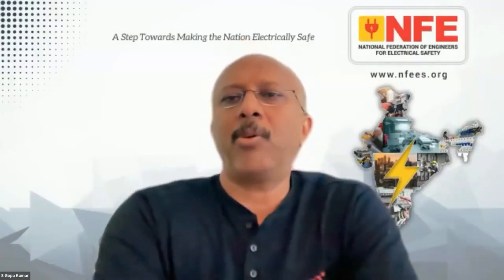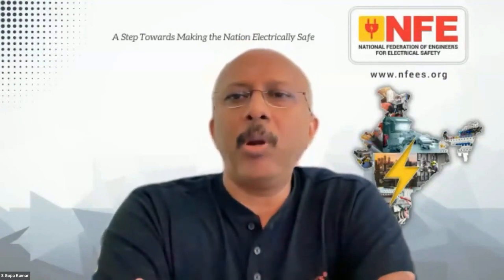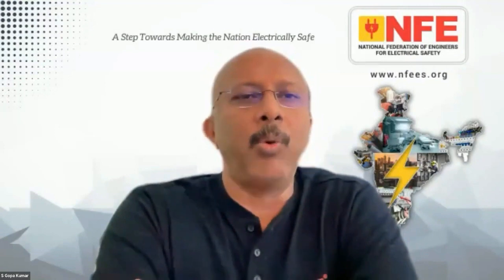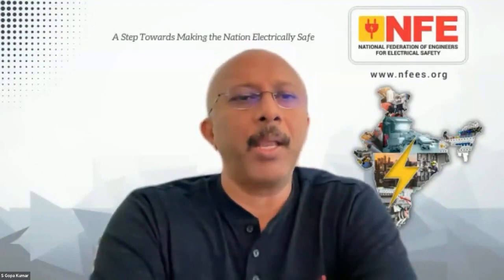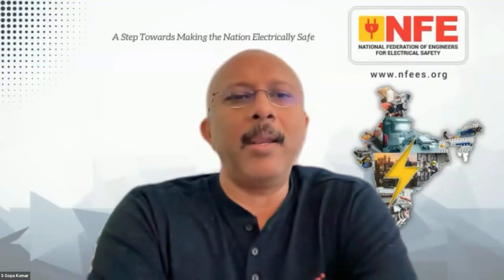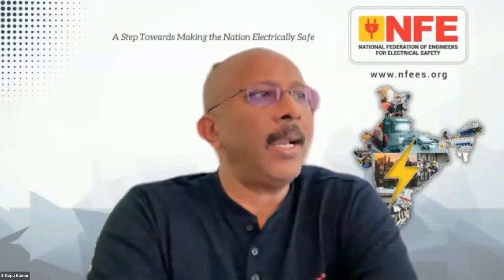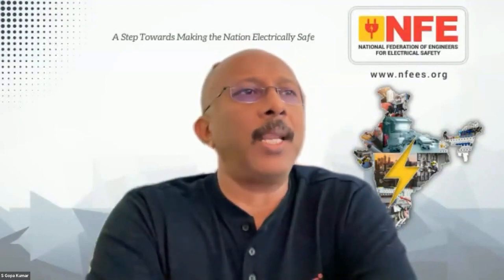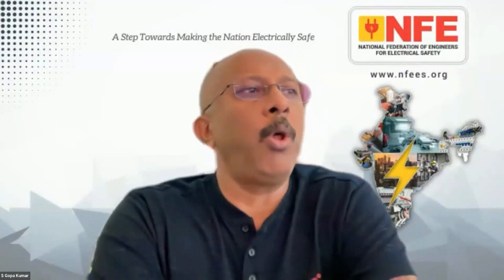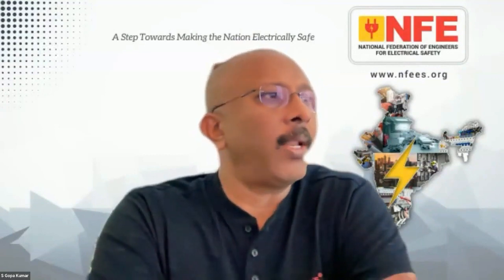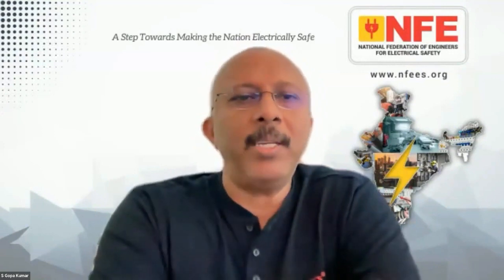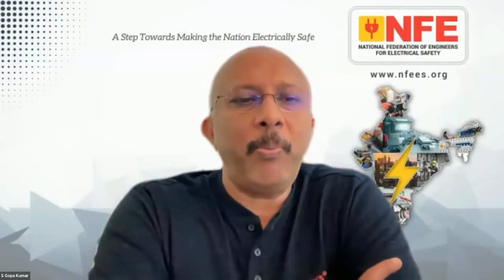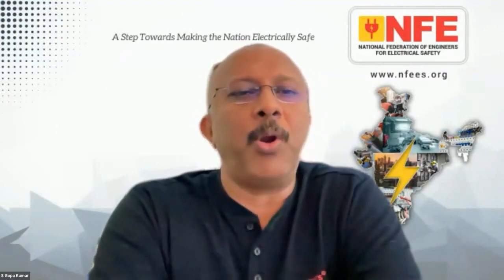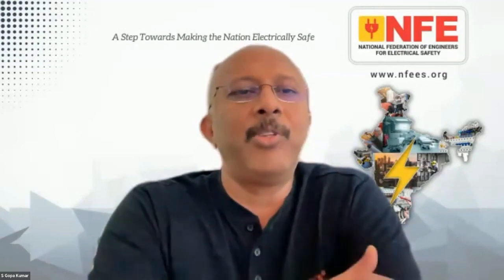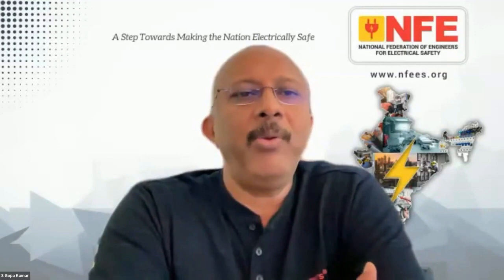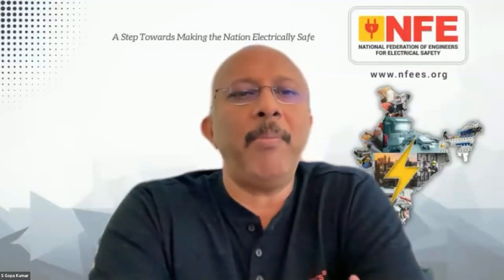There may be chances for mistakes also in this standard. For example, if you look at the IE rule or the CEA regulation 2010, regulation number 41, sub-regulation number 10, what it writes is, no person shall make a connection with earth by the aid of, nor shall he keep in contact with any water mains not belonging to him, except with the consent of the owner thereof and the electrical inspector. So the regulation says, if without permission from the owner of the pipe, you are not supposed to bond. The regulation never says that you shouldn't bond. That is not there. But in a way, you get the permission from the owner of the metal pipe and you bond it. That is what is written.